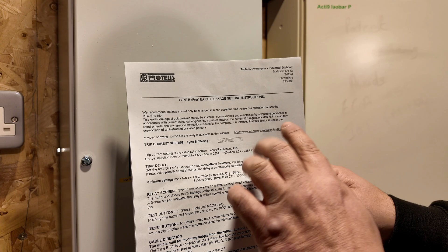So you can see here we get a little instruction sheet that comes with it. There is a YouTube video to watch. I'll link it in the description if anyone wants to go off and see how this is adjusted and played with. But basically you've got a few settings. So you can have 30 milliamps to 1.5 amps on your RCD protection. If you're in the 63 to 250 amp range, you can have 100 milliamps to 1.5 amps RCD leakage, earth leakage that are allowed to happen at the 315 to 630 amp range.